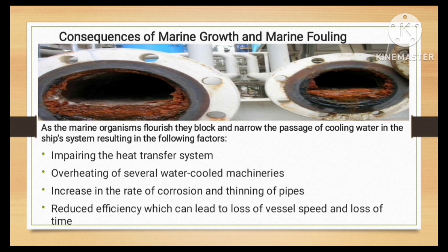Consequences of Marine Growth and Marine Fouling: As the marine organisms flourish, they block and narrow the passage of cooling water in the ship's system, resulting in the following factors: 1. Impairing the heat transfer system. 2. Overheating of several water-cooled machineries. 3. Increase in the rate of corrosion and thinning of pipes. 4. Reduced efficiency which can lead to loss of vessel speed and loss of time.